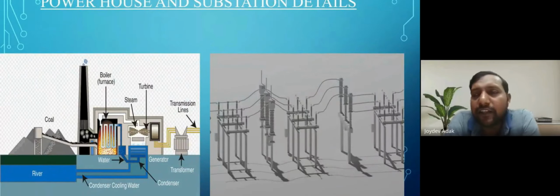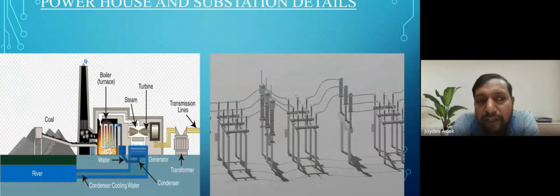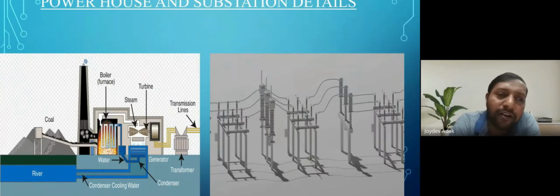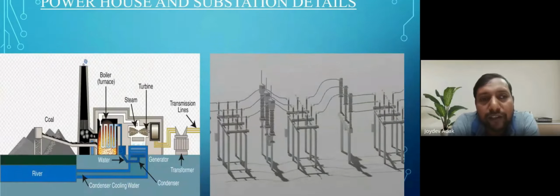So as the insulation problem is there, in case of a generator we can use the cooling medium as hydrogen or water. If we increase the insulation based on hydrogen or water cooling, then the size of the generator will be bulky and huge, and it cannot be transported from one place to another. That is a handling problem. These two problems, handling and insulation, bind us to keep the voltage at a certain level.